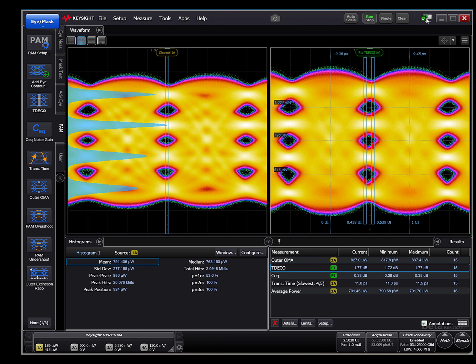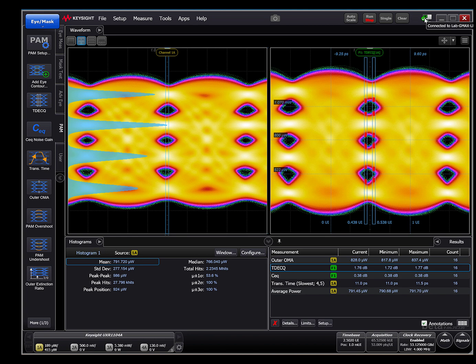Leaving the instruments on a free run, we can iterate on this set of conditions and repeat these measurements, taking about 4 seconds per iteration. Here we will just run a couple of cycles of the FlexRT measurement system to underscore the speed and versatility of these measurements in supporting the N7005A.